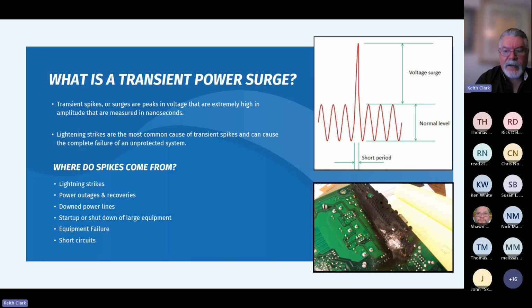Contractors do not want to have to go back out and fix things. You have happier end user customers in the long run, and it's just a smart policy to implement. And where do spikes come from? They come from a variety of sources: lightning strikes, power outages and recoveries, down power lines, a number of different reasons. Startup or shutdown of large equipment in some manufacturing facilities. They have such high amp draw that when they shut down, that voltage has to go somewhere, and it goes down the line and can cause spikes in equipment downstream from it.